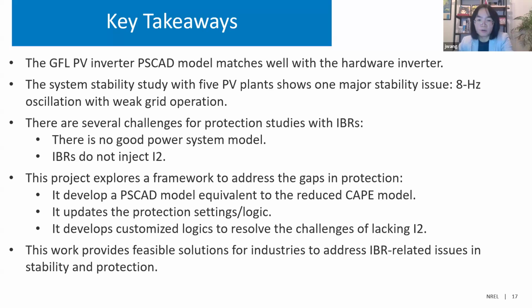Hopefully, this can be resolved by adding the grid forming inverter, and we also managed to do some tuning of the damping ratio and other parameters as well. And for the protection, the challenges are the low fault current and that the IBR do not contribute negative sequence current, but we can propose enhanced logics to solve those challenges, and also request the inverter vendor to add the negative sequence control in their controller.